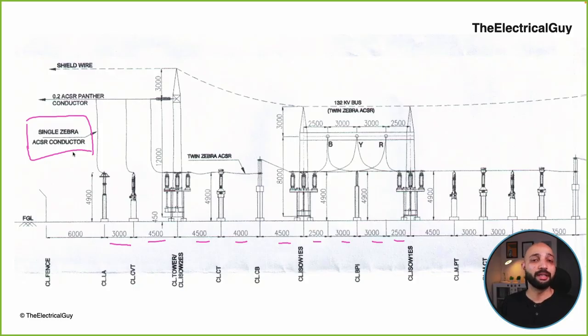Now what is the single Zebra ACSR conductor? This is basically a conductor that is used in the substation. The names of conductors are given after different animals, for a strange reason. The bigger the animal, the bigger the diameter of the conductor. That is the understanding. So you will see names like single ACSR Zebra, single ACSR Moose, single ACSR Tiger, single ACSR Panther, single ACSR Dog. The bigger the animal, the bigger the diameter of that conductor. You will see a single Zebra conductor used as a dropper here. Then there is an ACSR Panther conductor, this particular one. And then there is a twin ACSR bus also used. So these are the names of the conductors.